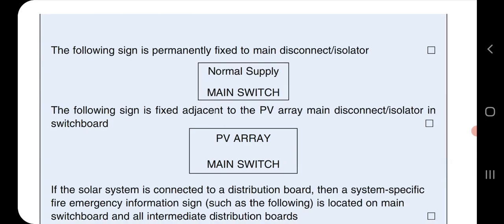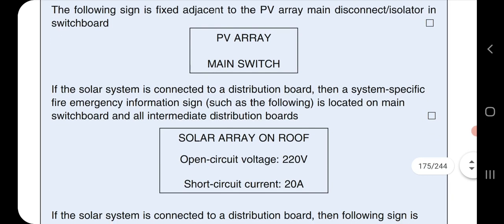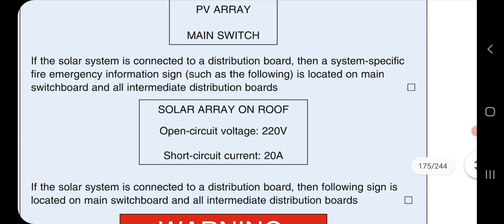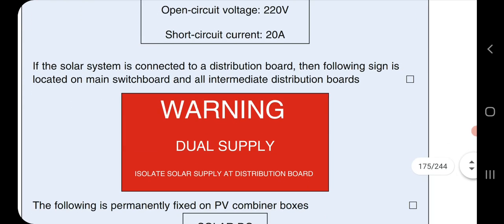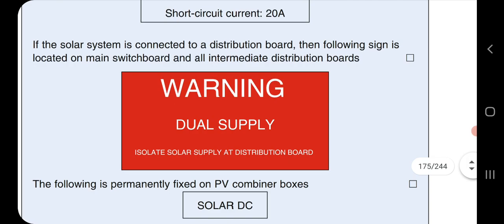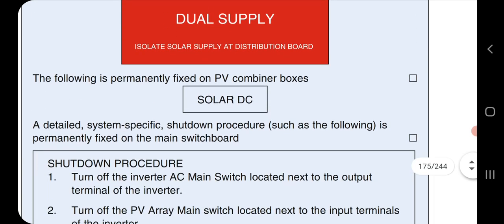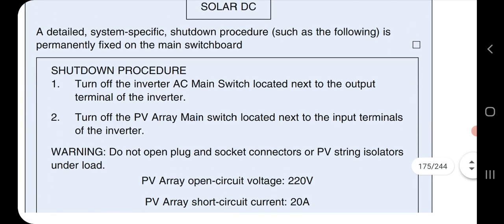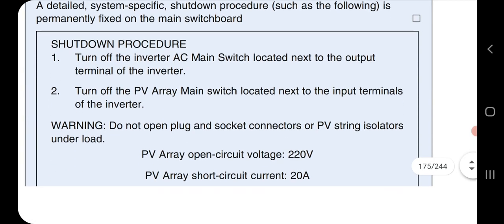Permanently for the main connector, disconnector, normal supply, main switches, PV array main switches, they check all the things, how it is working or not. Like the solar array on the roof, what is the open voltage? Yes or no, they will take it. For that one also they kept a warning board, and they will write a shutdown procedure on it too.